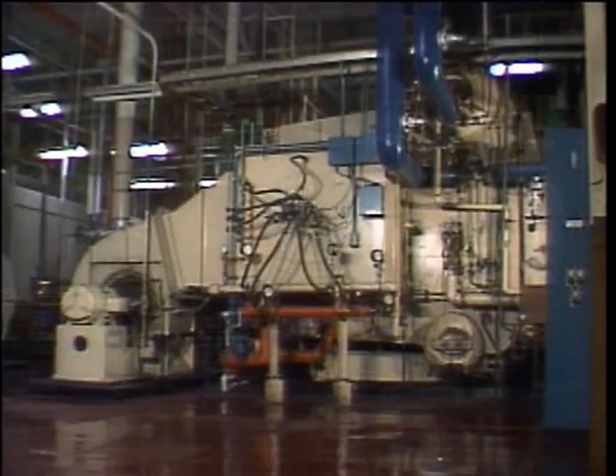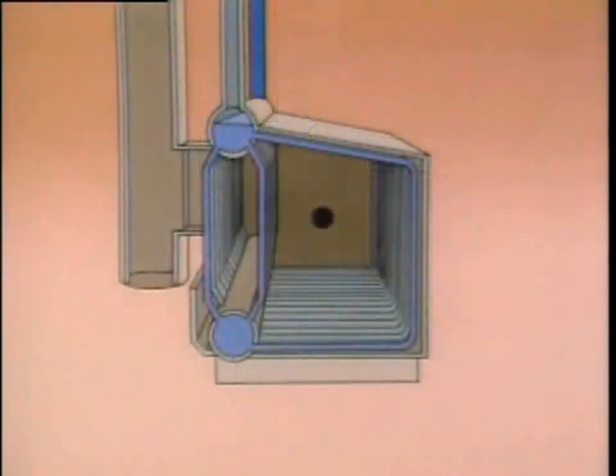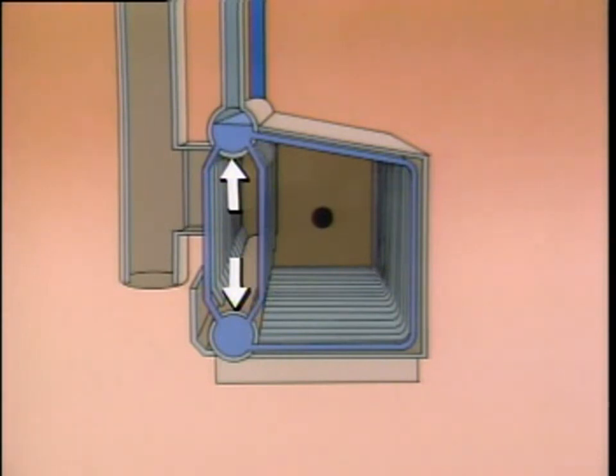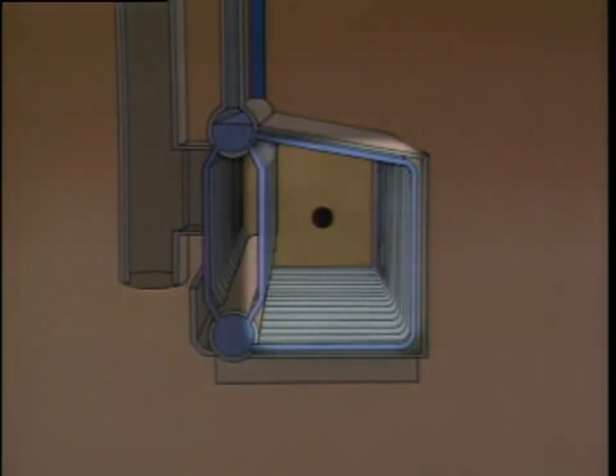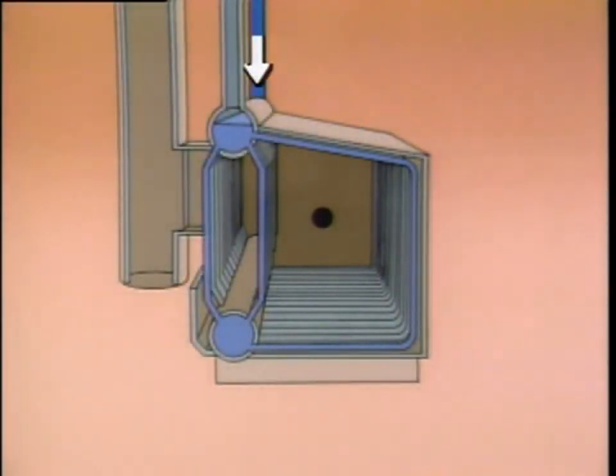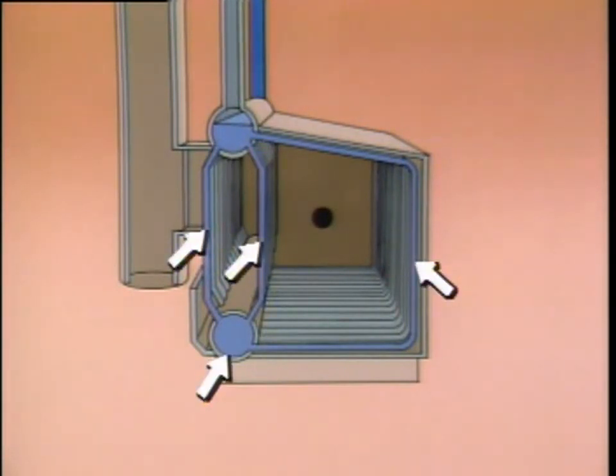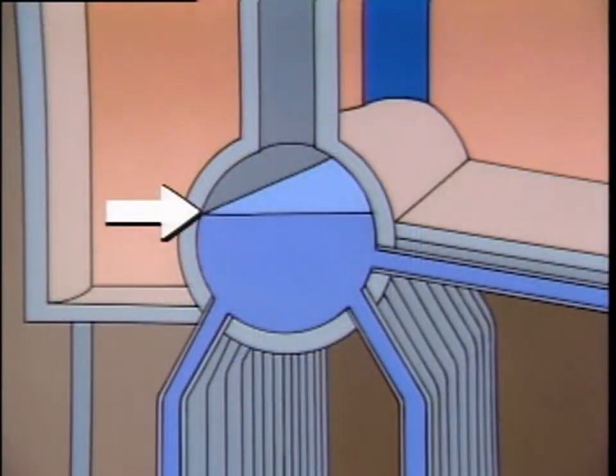Water tube boilers use tubes to route water and steam through the boiler. The combustion gases flow past the outside surfaces of the tubes. Water tube boilers may vary in design, but most of them operate in basically the same way. This particular boiler consists of a series of water tubes and two drums. The drums distribute water to the tubes. The water tubes connect the drums and form a wall around the combustion area. Water is fed into the upper drum through a feed water inlet line. The water tubes and the lower drum are completely filled with water, while the upper drum is only filled to a certain level. This provides space for steam to collect, so the upper drum is often called the steam drum.